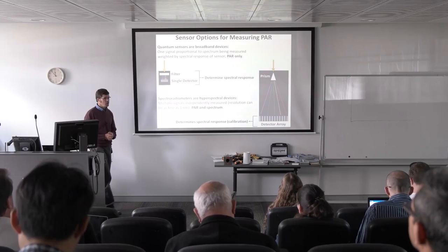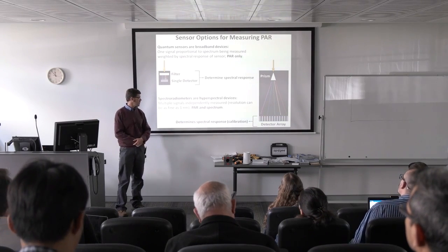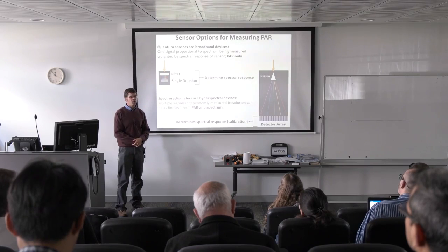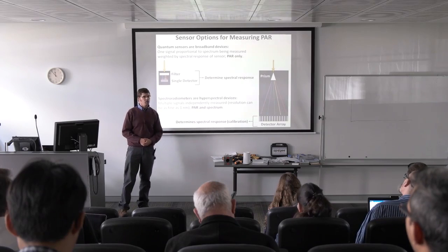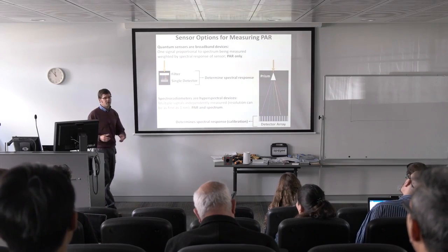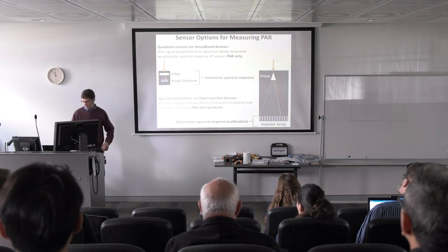And so the only thing that really determines the spectral response or the sensitivity of a spectroradiometer is how well is it calibrated. If we can accurately calibrate each of the wavelengths, then we have an accurate quantum sensor independent of the light source that we're trying to measure.